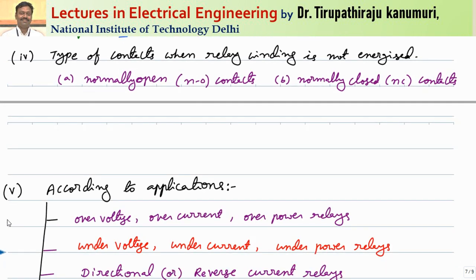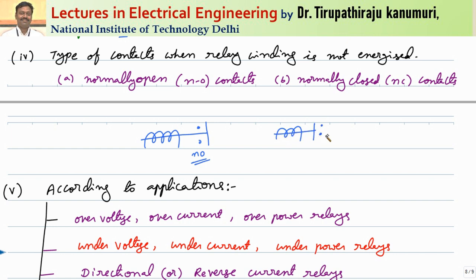Regarding the type of contacts when the relay winding is not energized: if the contacts are open when the relay is not energized, it is called a normally open type. When the relay current crosses the limit, it is attracted and closes the contacts. The second type — where the contacts are normally closed — means they are in the closed position when not energized, but whenever the relay is energized, they open. This is called the normally closed type.